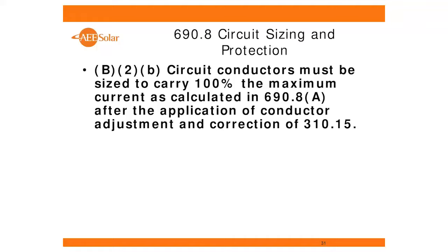Now, however, if we're going to use what are called the conditions of use, temperature and conduit fill, then we can use 100% of what we calculated in 690.8(A), which is still 125% of the short circuit current. Okay, so we are oversizing our wire, but in the past, copper was cheap compared to modules. It really was. And so, as purists in the PV industry, how many people have been doing grid-connected PV for more than 10 years? A couple people in the room.